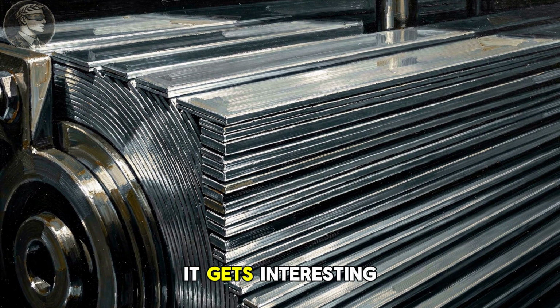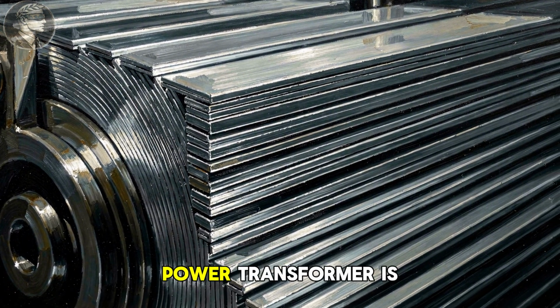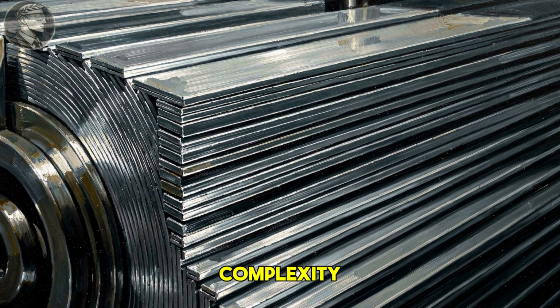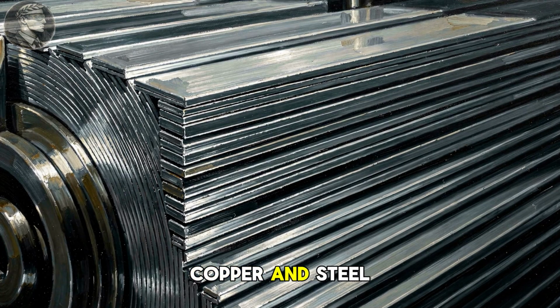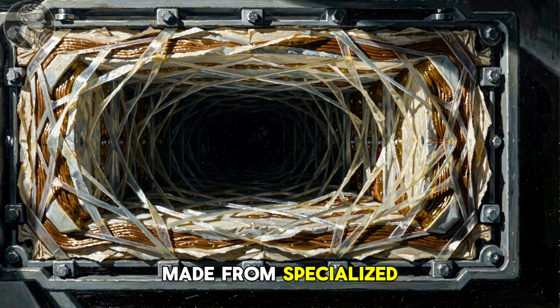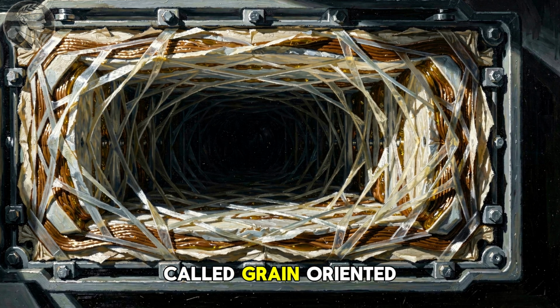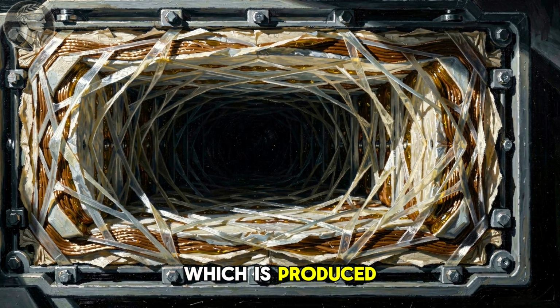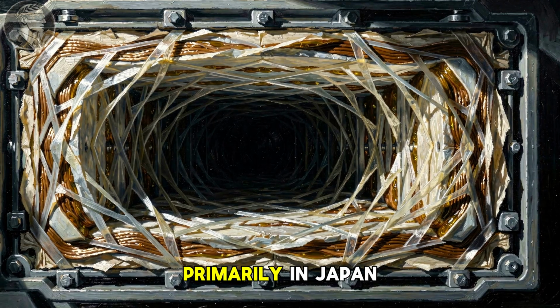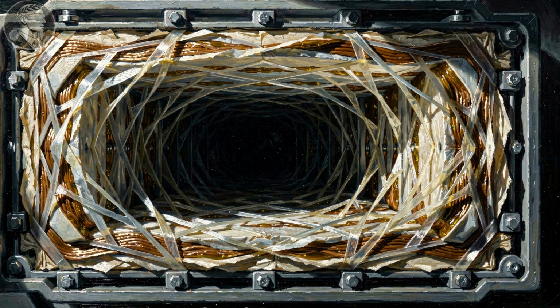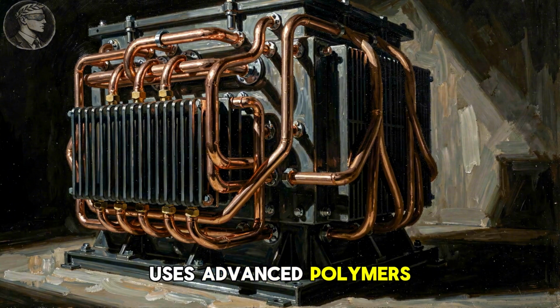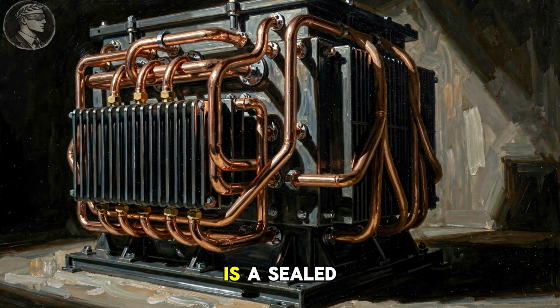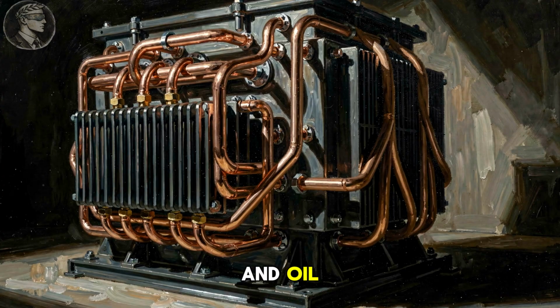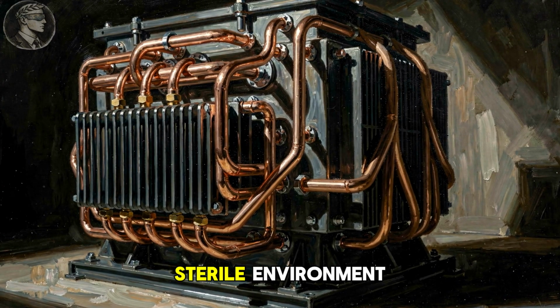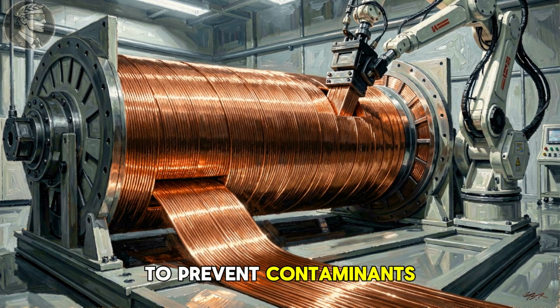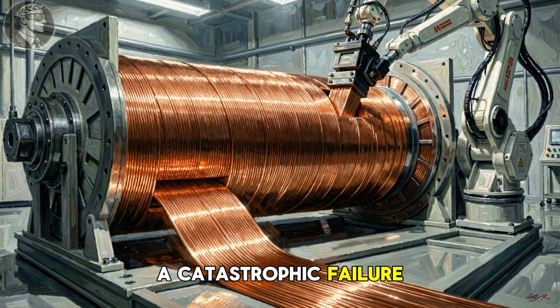Now here's where it gets interesting. A modern large power transformer is a monster of complexity. It's not just copper and steel. The core is made from specialized electrical steel called grain-oriented steel, which is produced by only a few mills worldwide, primarily in Japan and Germany. The insulation system uses advanced polymers and paper. The cooling system is a sealed network of pipes and oil. And it all must be assembled in a near-sterile environment to prevent contaminants that could cause a catastrophic failure.